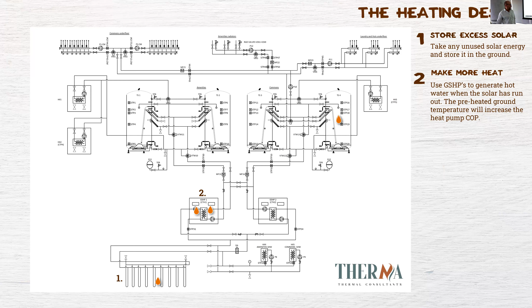Next, store the heat. The heat pump now heats up the buffer tank. We had 4 big buffer tanks on this job. Interesting fact about the buffer tanks: these have an anti-siphon connection on them. A standard buffer tank would just have a port straight in the side of it. These are a 45-degree drop, so that stops any destratification in the tank, but also any heat leaching out. These tanks are actually used in Antarctica, in the buildings out there, because they were Belgian tanks that were ranked as probably the most insulated and well thought out buffer vessel you can get.